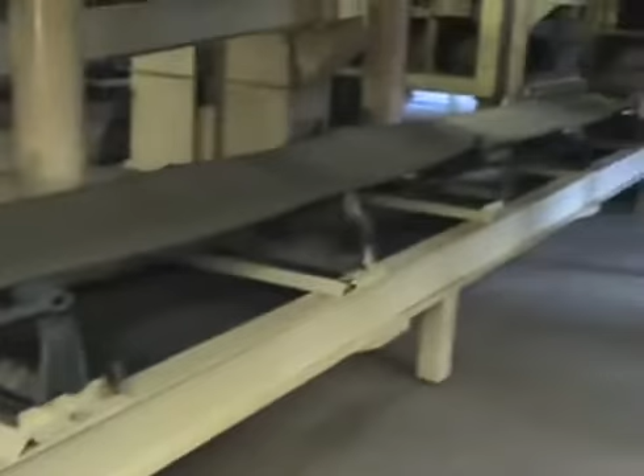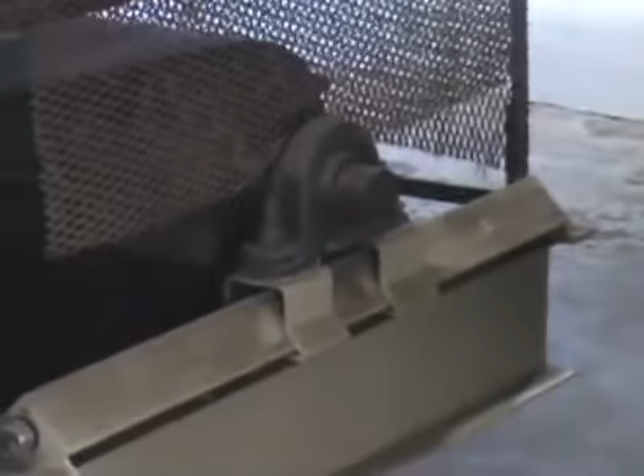First, we need to select a suitable location for the MSI on the conveyor. Consult the belt scale application guide to determine the best scale location. Once a location for the belt scale has been selected, we can begin the installation. Create a reference mark on the stringer at the belt take-up so that the take-up pulley can be returned to its original location once the belt scale has been installed.